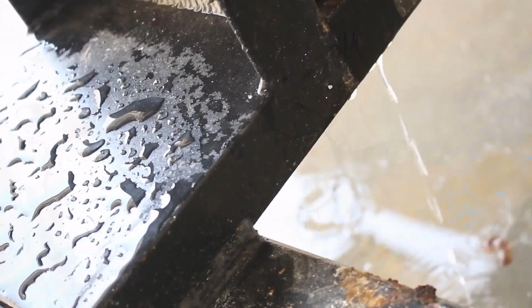So as you can see there, it was interesting seeing how that 4-inch PVC pipe that had that assembly, the ring, not just fire caulk around it, filled in the gap and that smoke stopped coming through the pipe. So what do we want? We want safety. These are some resources that even some of the manufacturers go to when they are looking for answers themselves: the International Firestop Council and the Firestop Contractors International Association.